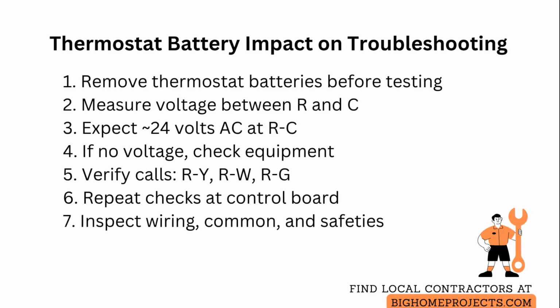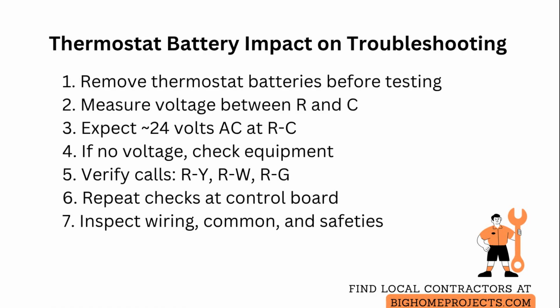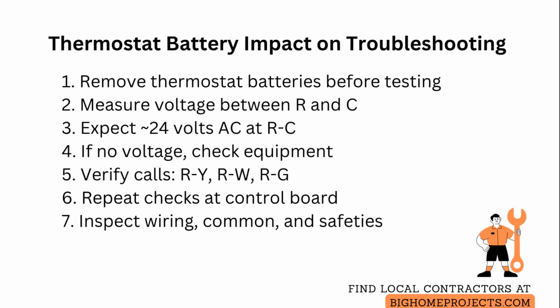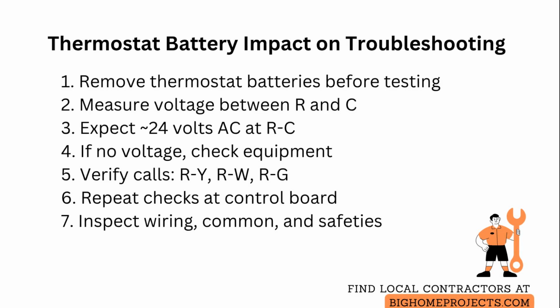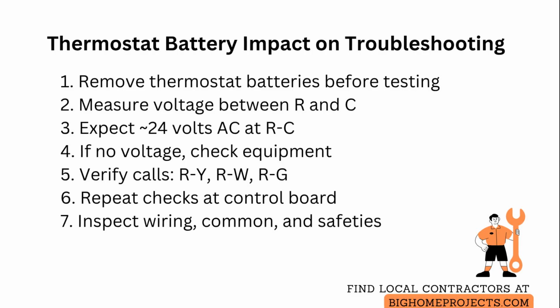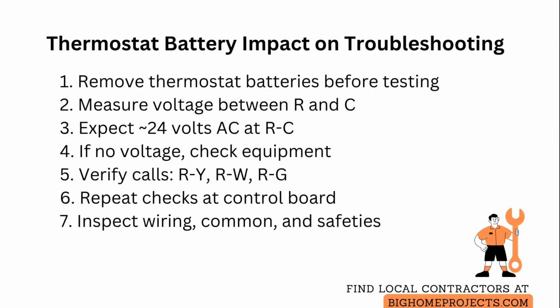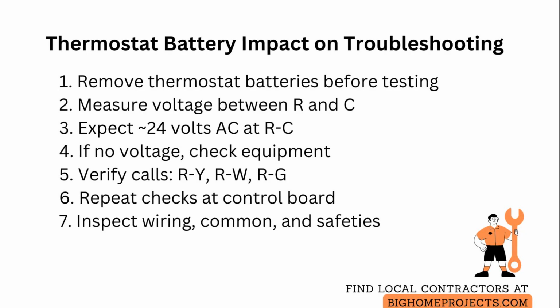If you do read proper voltage at R and C, call for heat, cool, and fan, and then check voltage from R to Y, R to W, and R to G during each call to verify that the thermostat is actually closing those circuits. When calls are correct at the stat but nothing happens, move to the equipment control board and repeat the same checks there to find any breaks between the thermostat and the unit, such as broken wires, loose common connections, or safety switches opening the circuit.